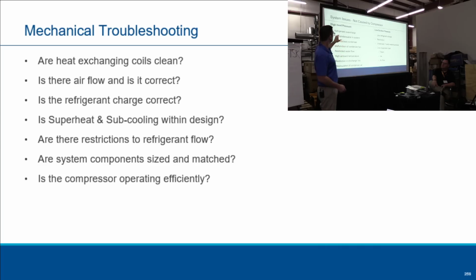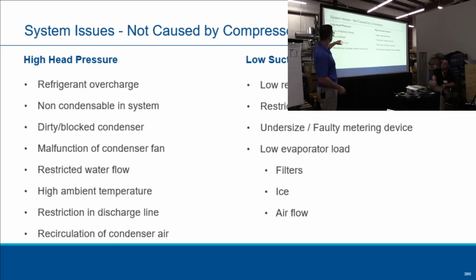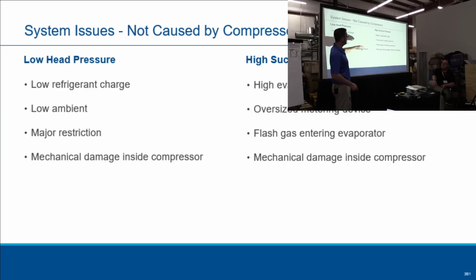Okay. Different causes. We talked about all these already for high pressure and low pressure. Some more, these are good ones. Not caused by the compressor: low refrigerant charge, low ambient, major restriction, high evaporator load, oversized metering device, flash gas in the evaporator. Right? Most compressors fail because of a system-related issue, not because we sell broken compressors.